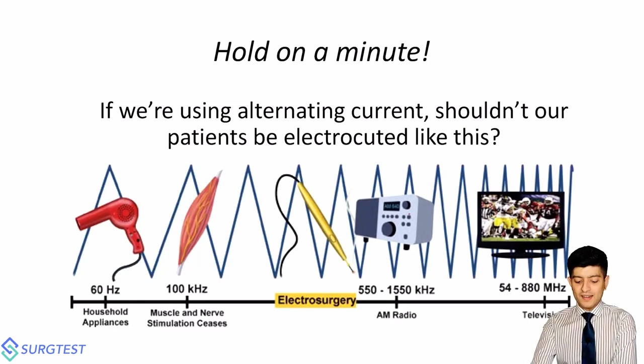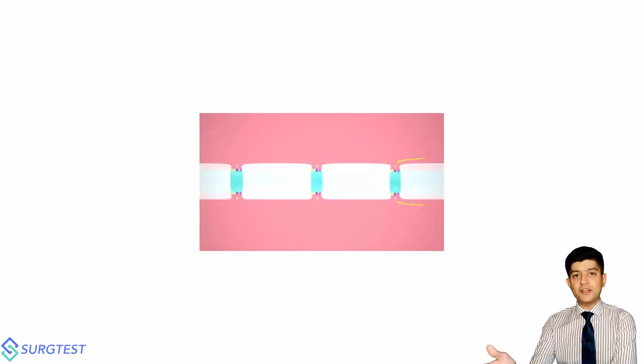Yes and no. Alternating current should technically electrocute you. For example, if you stick your fingers into your wall socket, which I am not advising you do, you will get tonic-clonic seizures at that given point in time. You will undergo this classic electrocution. But notice that electrosurgical energy that we'll end up using is at 5 lakh hertz. And at such a high frequency, the sodium potassium channels and the calcium channels on the cell walls just don't have enough time to open or close. The moment the current has started, before the channels open, it suddenly reverses direction. So the threshold is never reached for these channels to open, as a result of which the muscles never twitch.